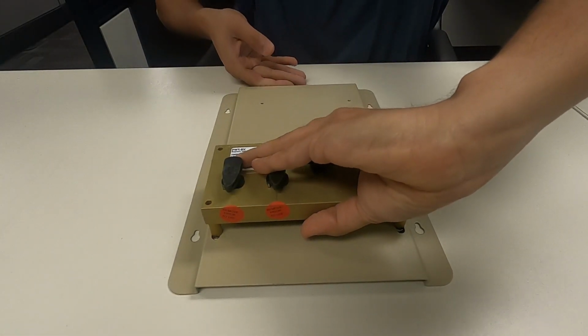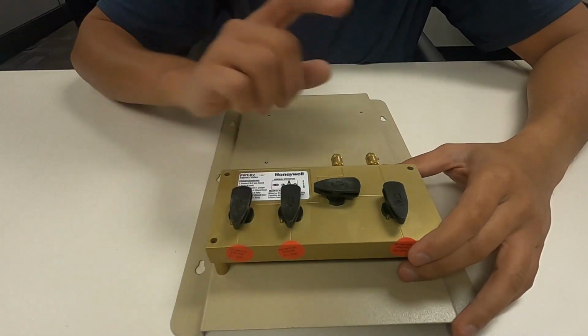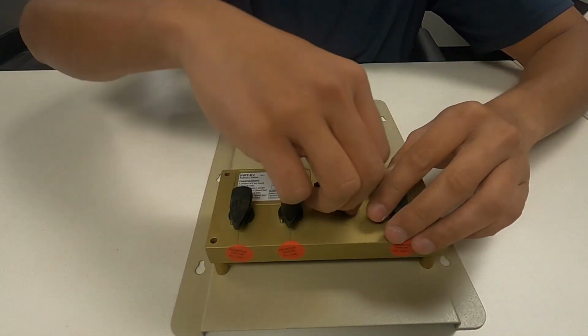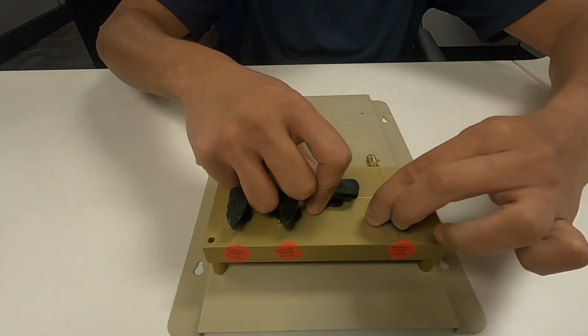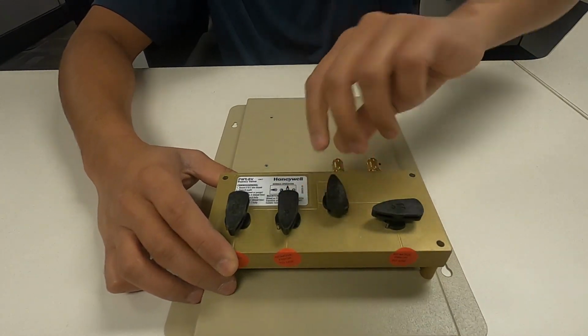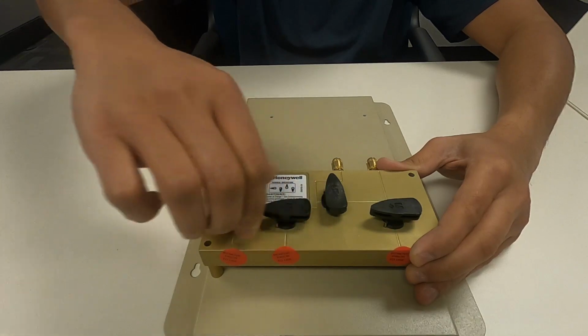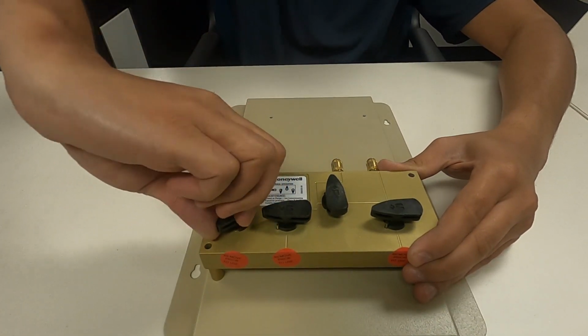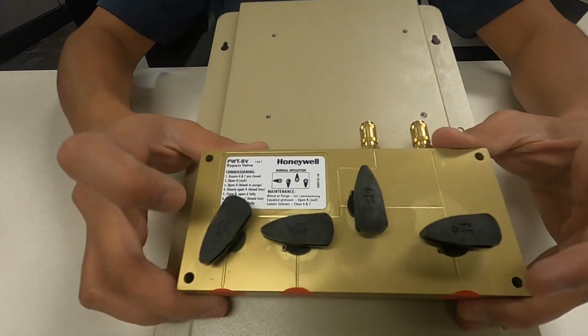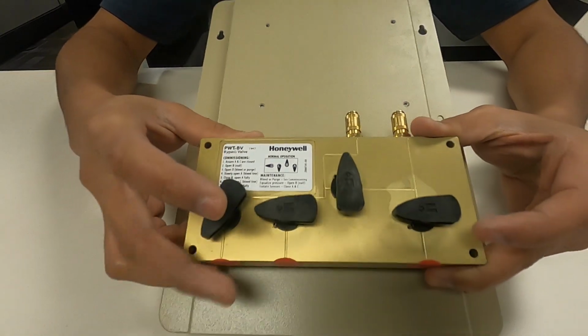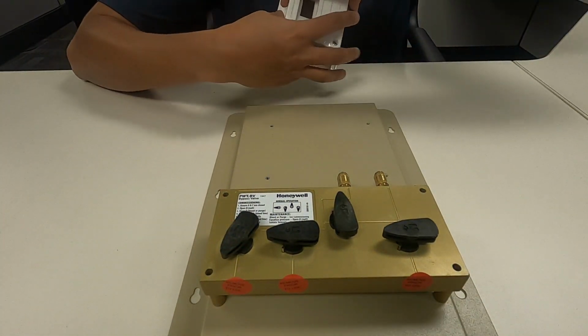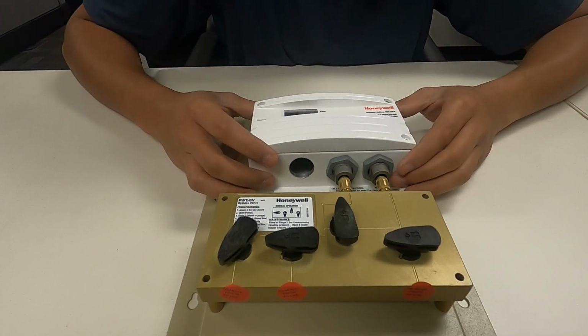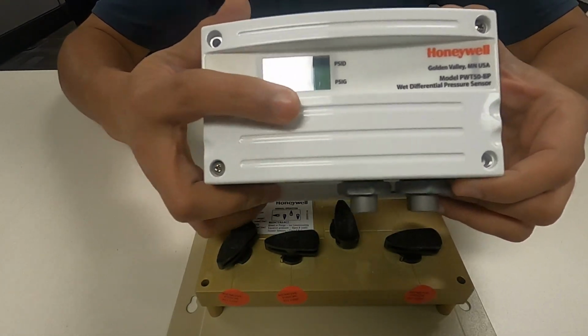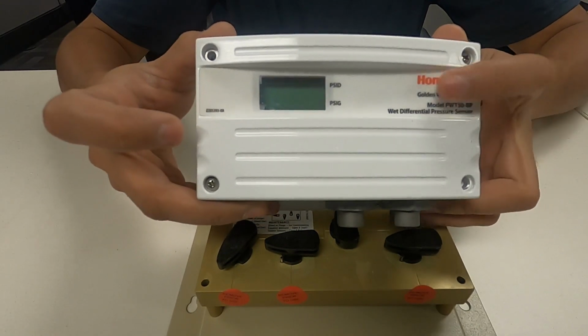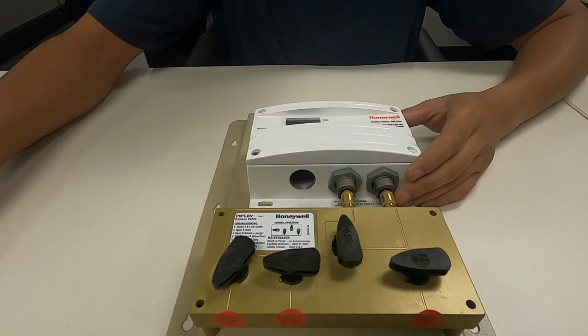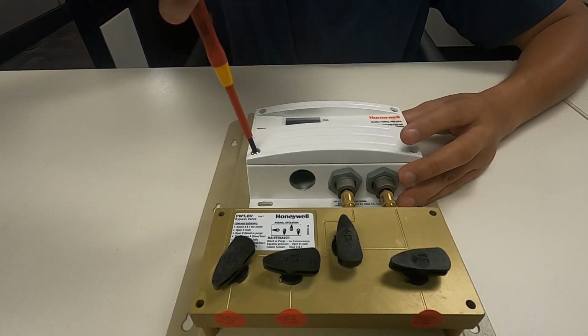All the pressure sensors will have a low tube and a high tube. Whichever side the airflow is coming in from will be the higher pressure, and the side it is going out to is the lower pressure. So whenever you measure, it is either high or low, depending on what you want to see. If you want to see a building pressure, you will connect your high probe on the building side and the low probe to the atmosphere, so that whatever pressure you get is the positive pressure maintained within the building relative to the outside atmosphere. Hope this is all making sense.